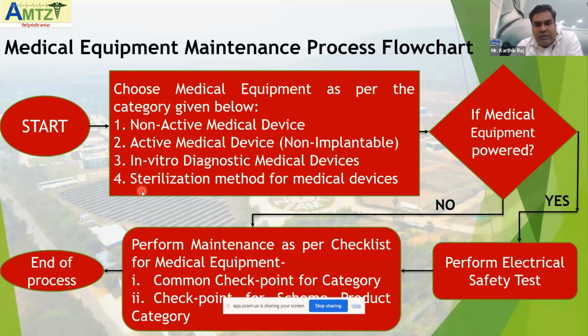Then once you know where it falls, now we have to understand whether the medical equipment is powered. When I say medical equipment is powered, that is whether it is using the power supply source or not. If it is using the power supply, then we have to perform the electrical safety test. Why? Because there is a chance of shocks for the patient if the equipment is not properly maintained. That is why we have to perform the electrical safety testing.